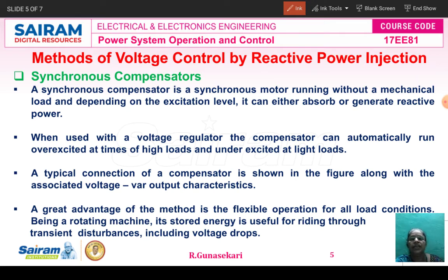The synchronous compensator is nothing but a synchronous motor. The synchronous motor can be operated at any power factor: unity, lagging or leading power factor. That means normal excitation, under excitation and over excitation. So the synchronous compensator is a synchronous motor running without a mechanical load, and depending on the excitation level, it either absorbs the reactive power or generates the reactive power. In both cases we can use the synchronous compensator.